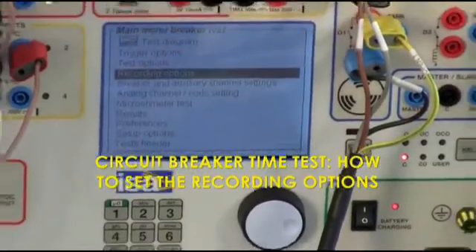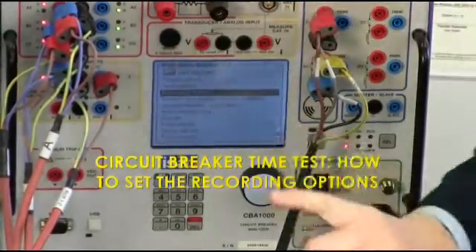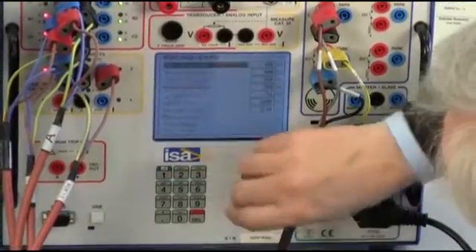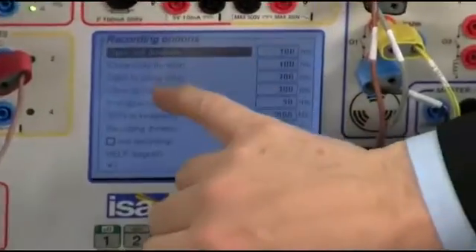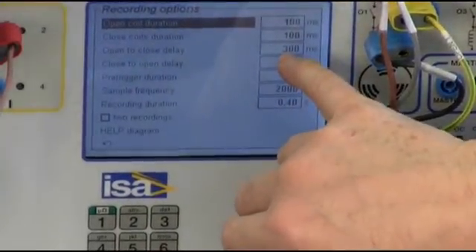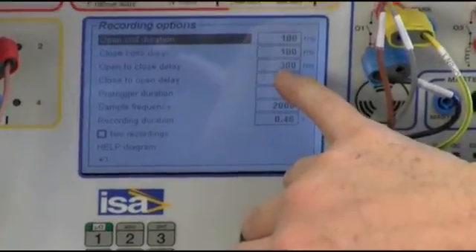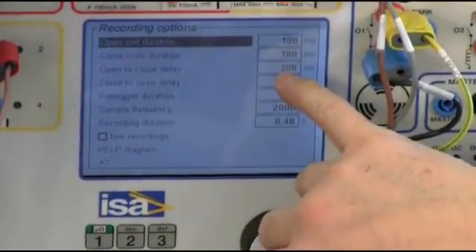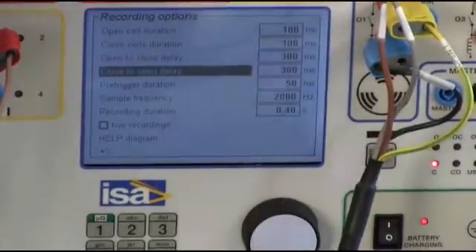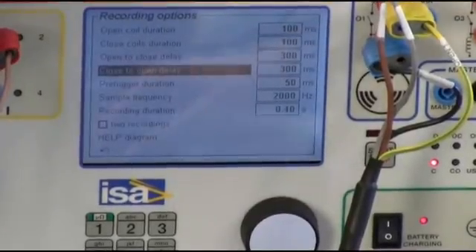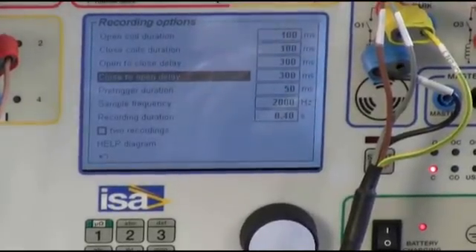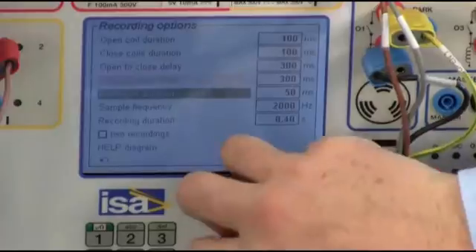Because I must be sure that the recording duration covers the complete sequence of open, closed, open. So, I go here and I see, open coil duration, closed coil duration. Open to close delay is 300 milliseconds, which corresponds to the standard re-close delay, and this is good. Close to open delay is 300 milliseconds, which is good because we can say this is the instance of closed onto fault.